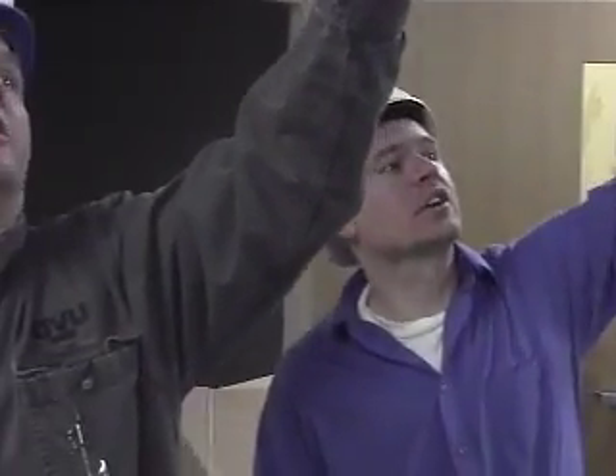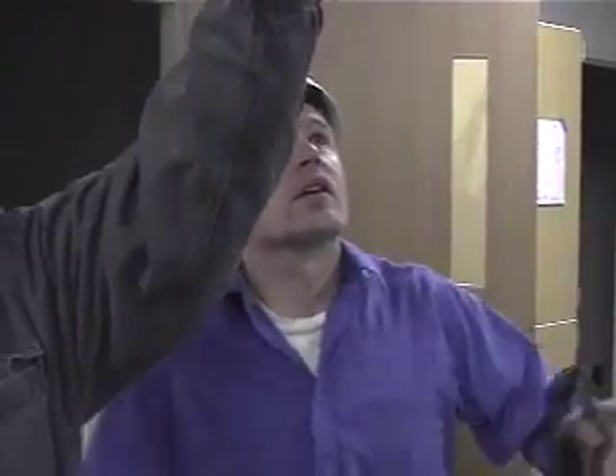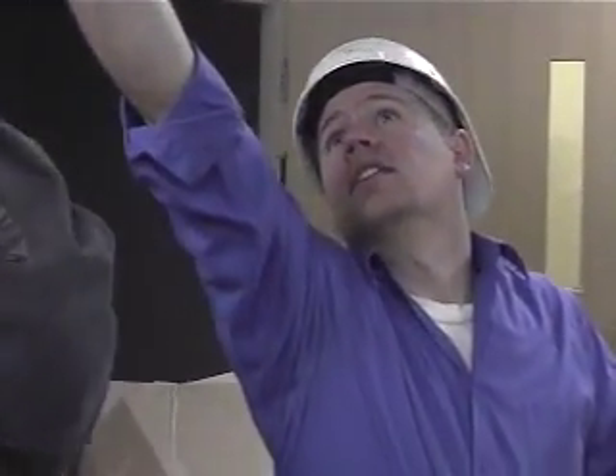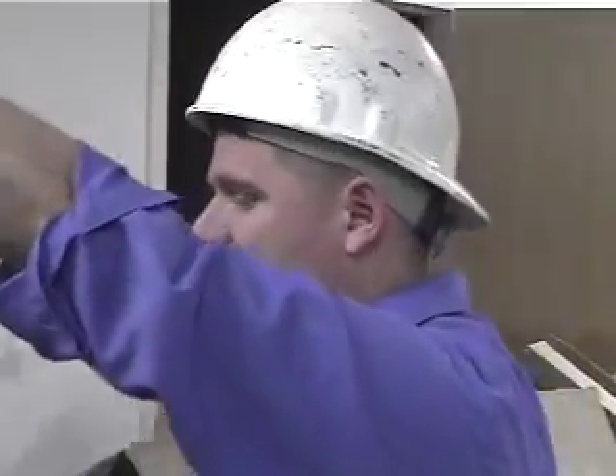So in this room here, the return here is not controlled on the valve, it's this return here. This is actually a supply register, and that's a supply, and then that's an exhaust over there. Typically in a lab, you don't do return, you do actual full exhaust. So all of your stuff going out would be the equivalent of an exhaust register. So where's the supply valve for these? That's actually right there. So it's coming through, you've got your coil, and then you've got your duct coming across and hitting all those registers. So that supply valve is right here above this light.